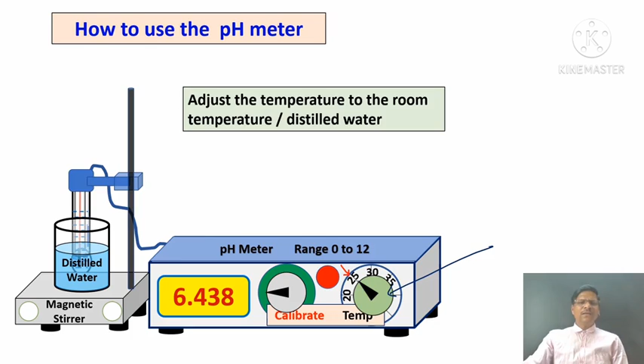Okay, the next step, we have to calibrate the pH meter, and for calibration purpose we have to use potassium hydrogen phthalate buffer. Okay, this is the potassium hydrogen phthalate buffer, KHP, of 0.05 molar. Okay, 0.05 molar KHP solution has exact pH 4.005. So we have already prepared the buffer solution and we use this buffer solution for the calibration purpose.